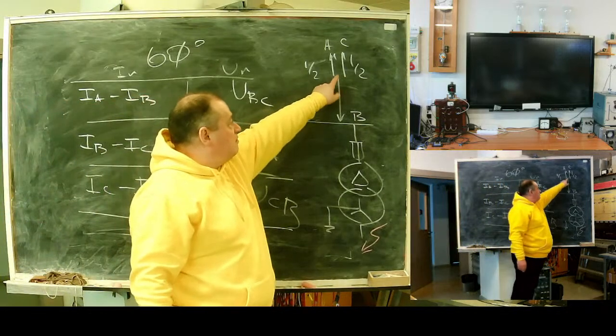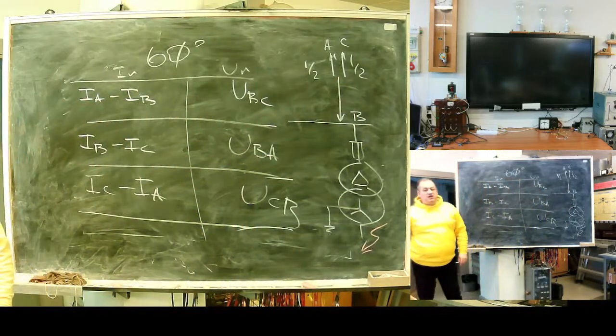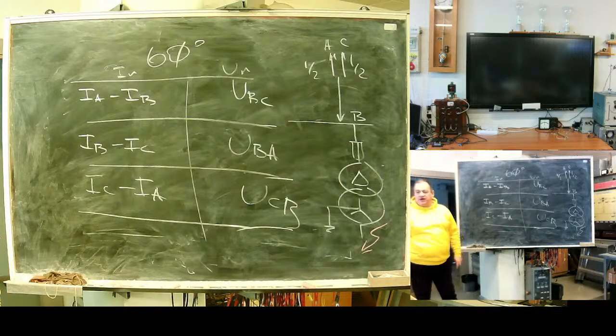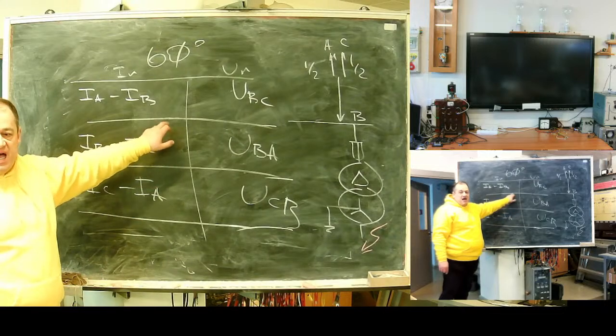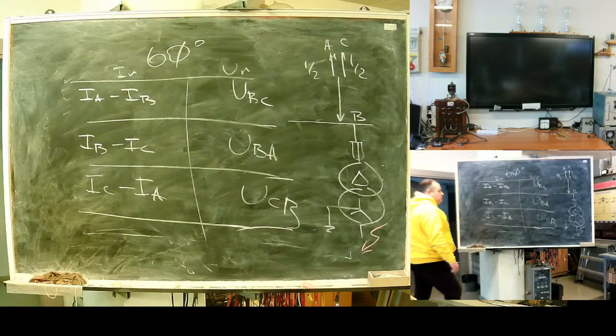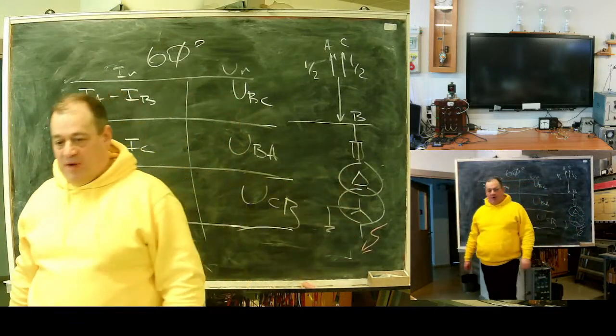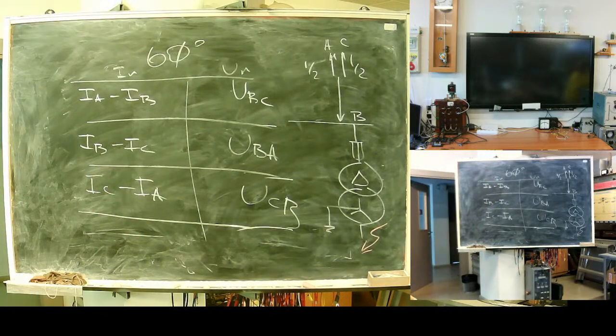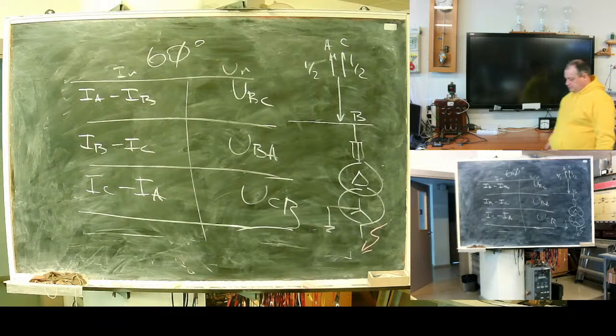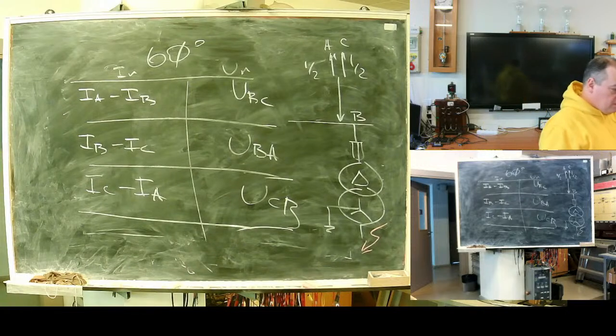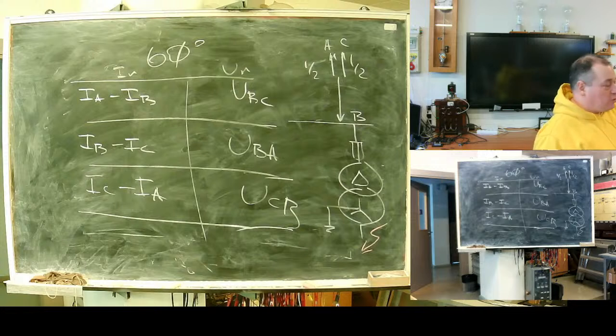In such case, current difference relays do not operate. They do not have sufficient current. So this design will fail if you have delta-star transformers. It's not suitable. If you have a network with grounded neutral, it's not a problem. If you have delta-star connection, it will fail. So in European distribution networks, this is not usable. In the United States, where you have distribution networks with grounded neutral, it will work.